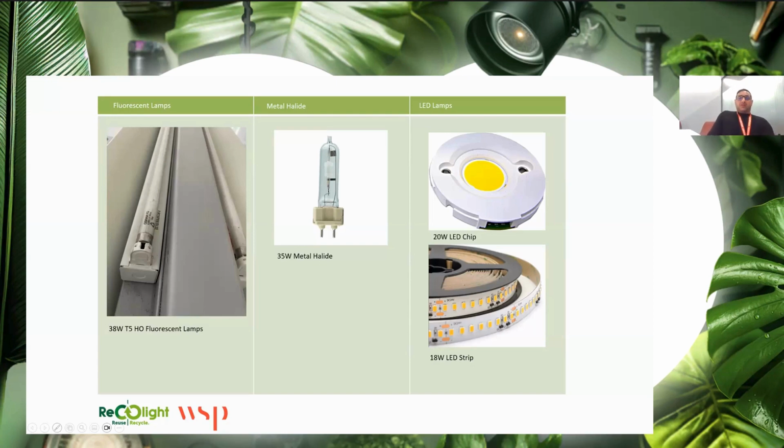So at that point, we started searching, ordering LED tubes from Sylvania, from Philips, and then speaking to local electrical stores, then understanding that there was also a shortage in the LED tubes, and they had to be pre-ordered. So we managed to get hold of 230-volt tubes, which required DALI relays for switching, and LED tubes that required transformers.